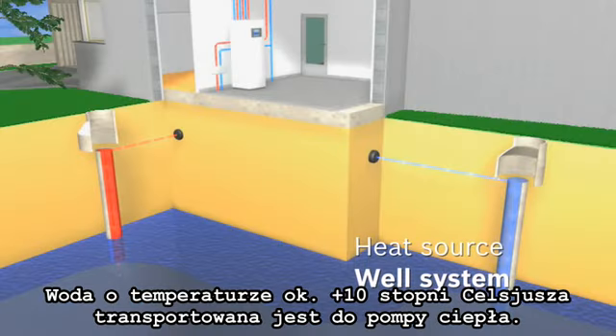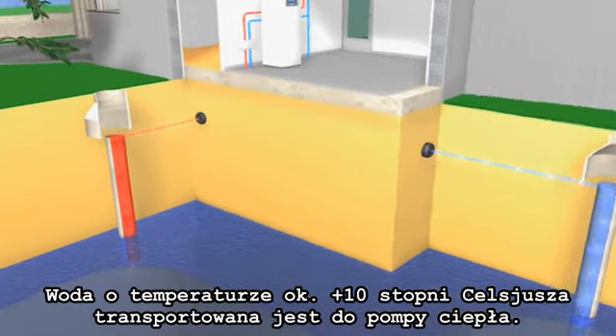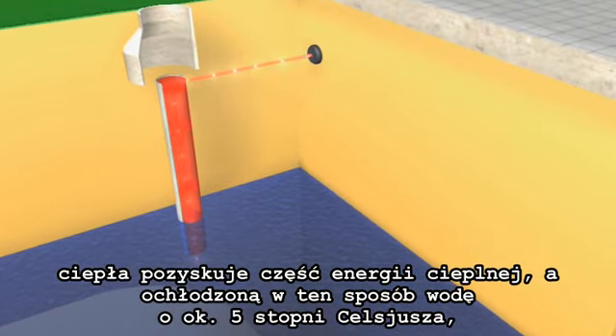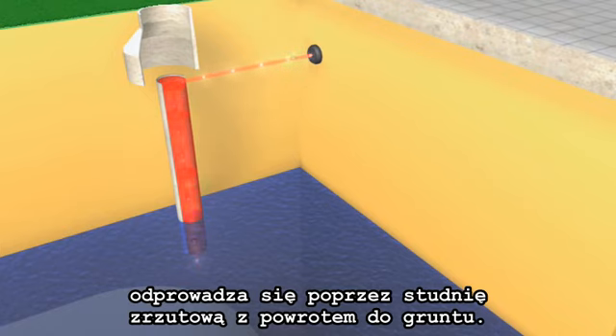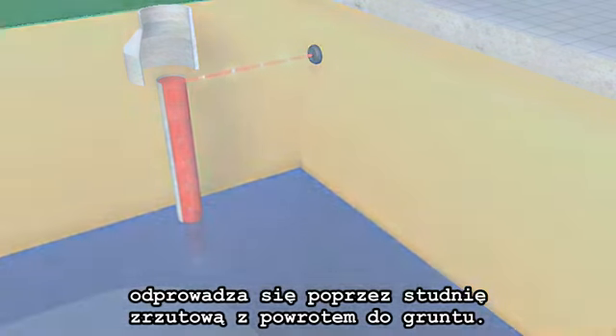Well system, by means of which the approximately 10 degrees Celsius warm water is transported in the direction of the heat pump. It extracts some of the warmth and leads the water, cooled down to approximately 6 degrees C, back to the soil via an injection well.